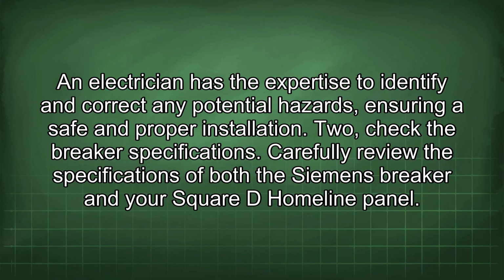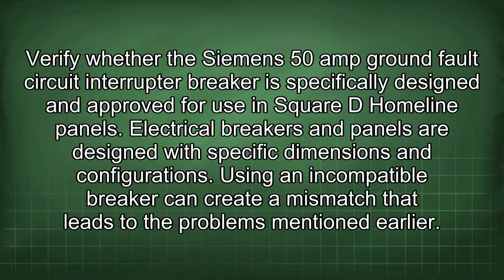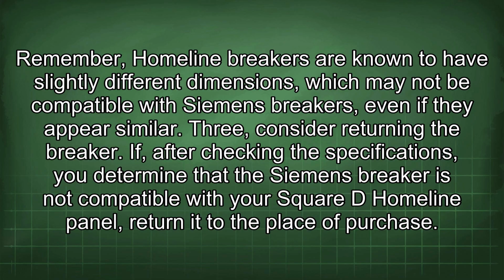2. Check the breaker specifications. Carefully review the specifications of both the Siemens breaker and your Square D Homeline panel. Verify whether the Siemens 50 amp ground fault circuit interrupter breaker is specifically designed and approved for use in Square D Homeline panels. Electrical breakers and panels are designed with specific dimensions and configurations. Using an incompatible breaker can create a mismatch that leads to the problems mentioned earlier. Remember, Homeline breakers are known to have slightly different dimensions which may not be compatible with Siemens breakers, even if they appear similar.